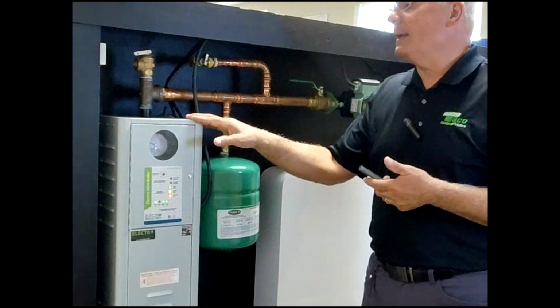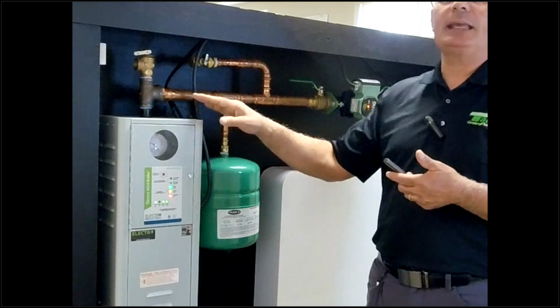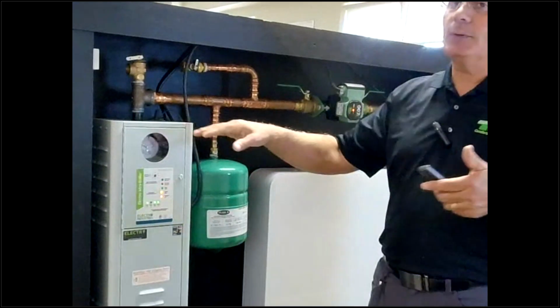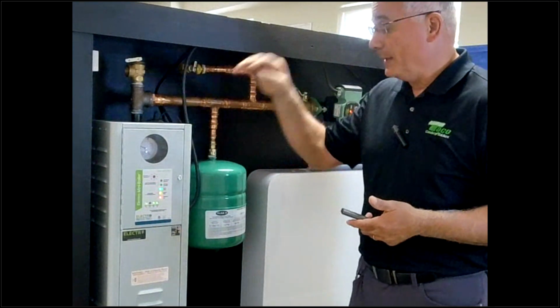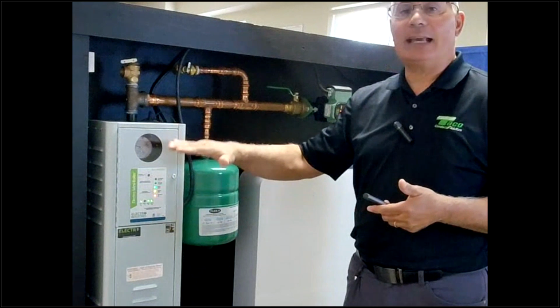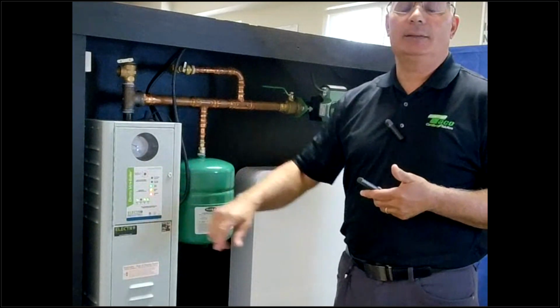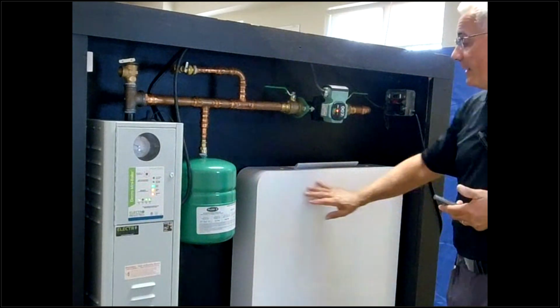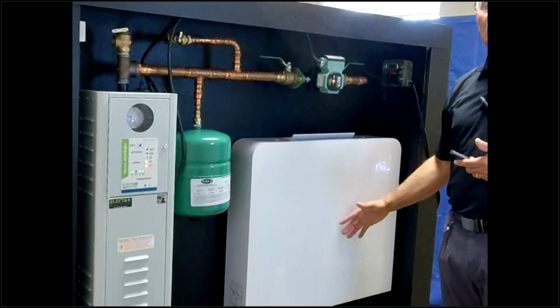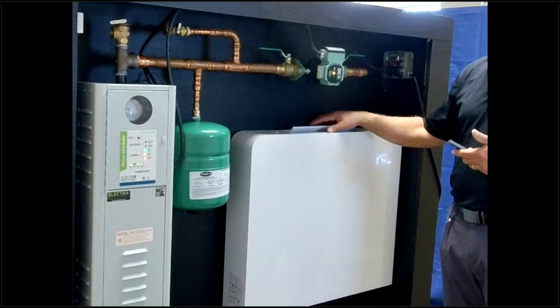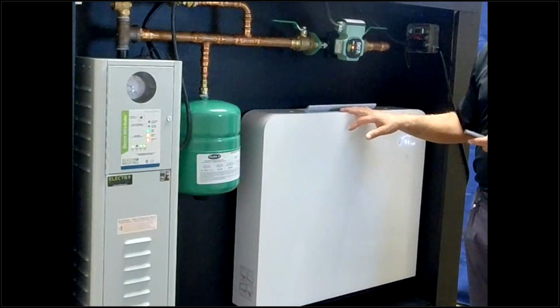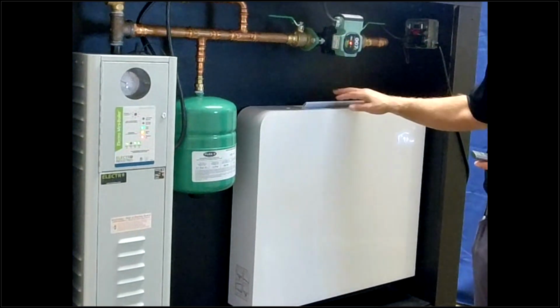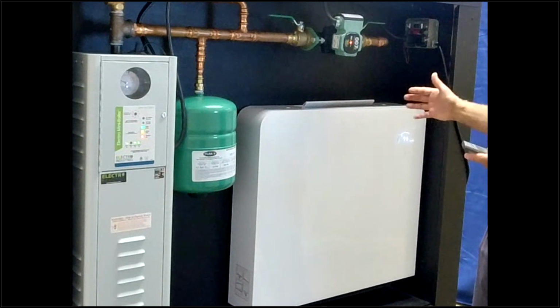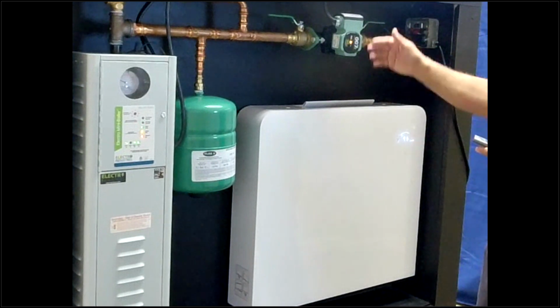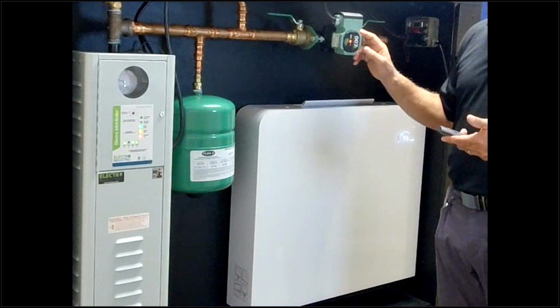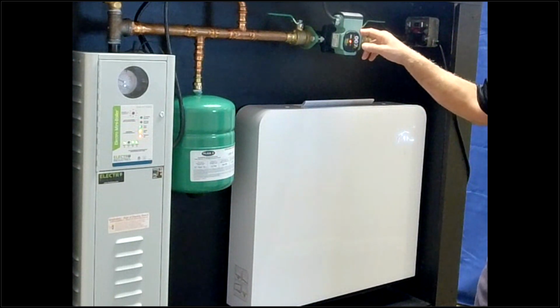So here I'm using electric power as my fuel source. I'm not using any oil, gas, or propane. Yes, you can argue we are burning something to make the electricity, but at this point, I'm using this as my fuel source, and this is outdoor resettable, and it'll change its output. Again, another energy saving feature. Since I have a hydronic coil here, I have the potential, because of a large coil and the fan blowing air across it, to have a lower temperature system. So if I have a lower temperature system, I will use less power. I can deliver that comfort in a nice quiet hydronic package. All right. And if I had multiple zones out here, this circulator is going to change its speed based on the number of zones that are calling.